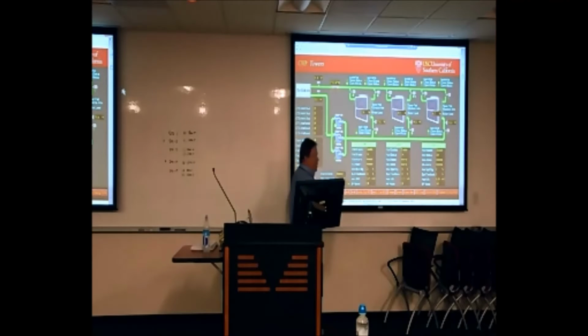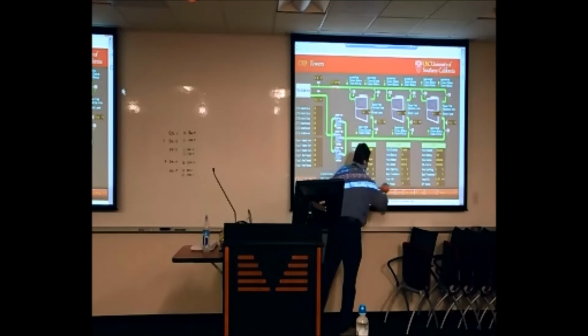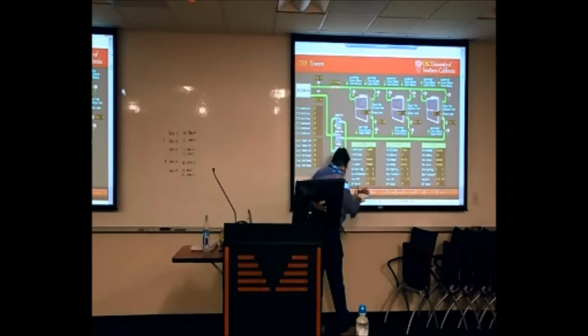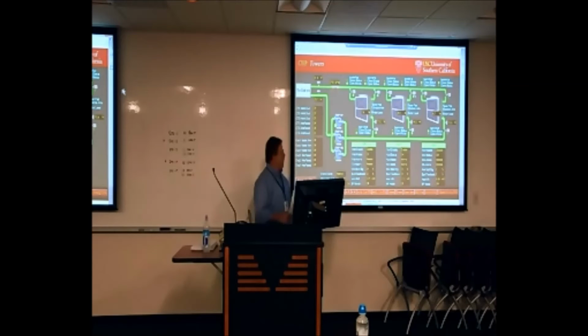And then lastly, there's a bypass mode on each drive where if you throw it in the bypass mode, we override the variable speed drive function and the fan goes full speed. Pardon me. And that's the bypass mode command we have down here. It's not commandable. It's switchable in the field, and then we'll have an indication here that it is in fact in the bypass mode, that we're running in bypass.